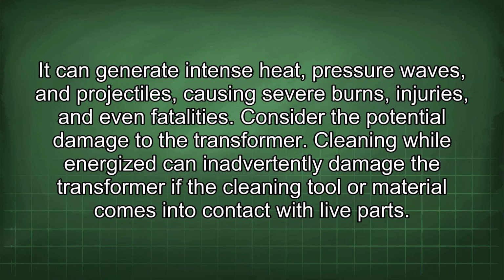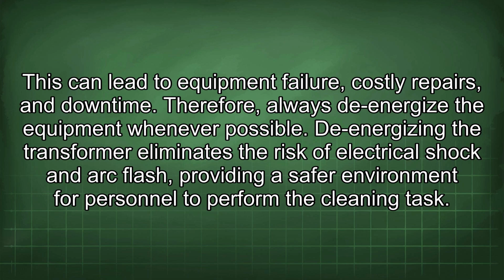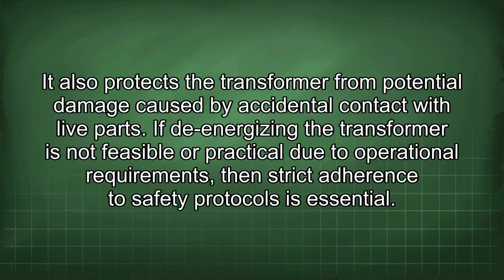Consider the potential damage to the transformer. Cleaning while energized can inadvertently damage the transformer if the cleaning tool or material comes into contact with live parts. This can lead to equipment failure, costly repairs, and downtime. Therefore, always de-energize the equipment whenever possible. De-energizing the transformer eliminates the risk of electrical shock and arc flash, providing a safer environment for personnel to perform the cleaning task. It also protects the transformer from potential damage caused by accidental contact with live parts.